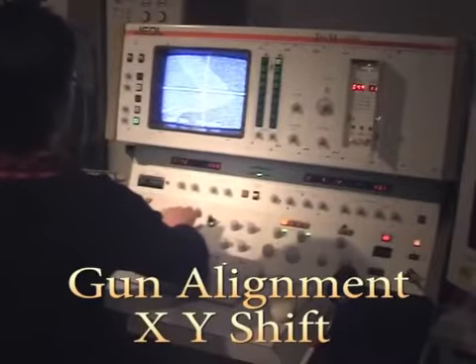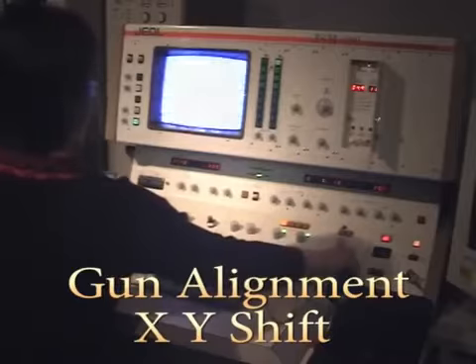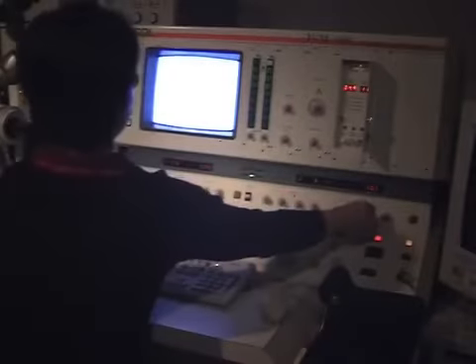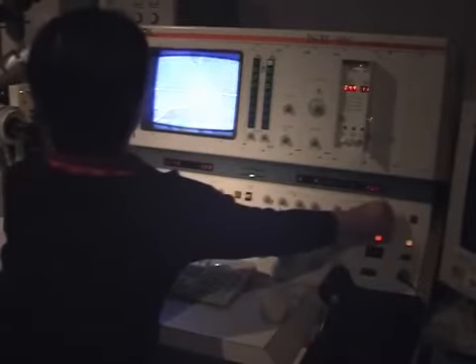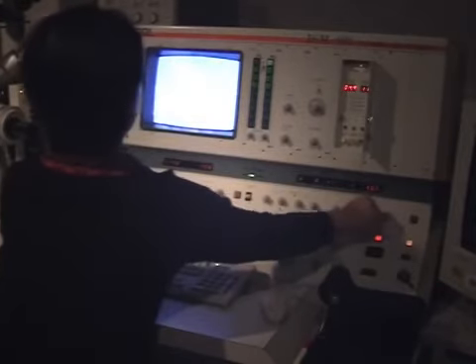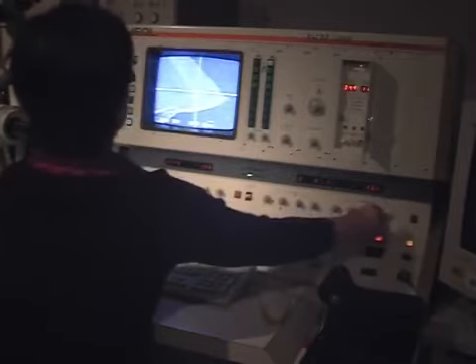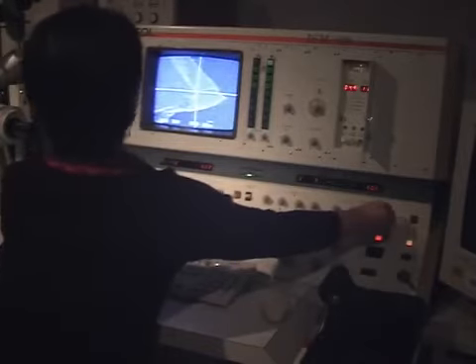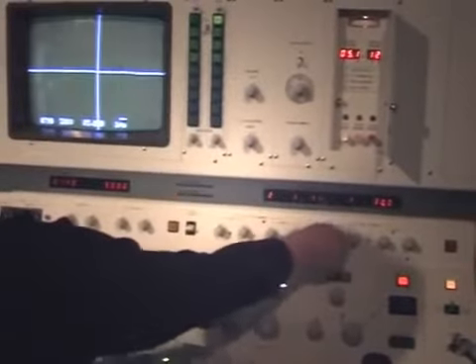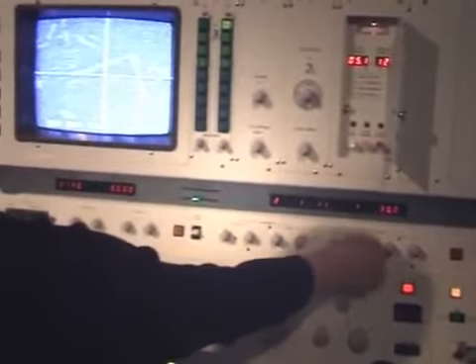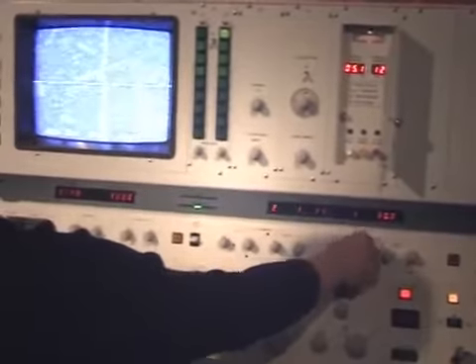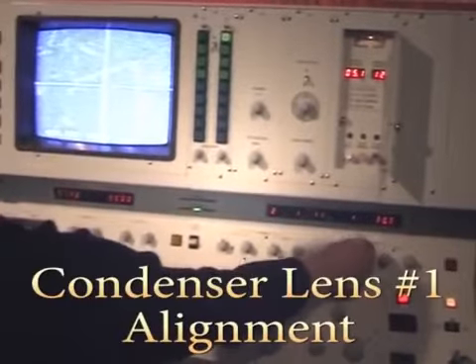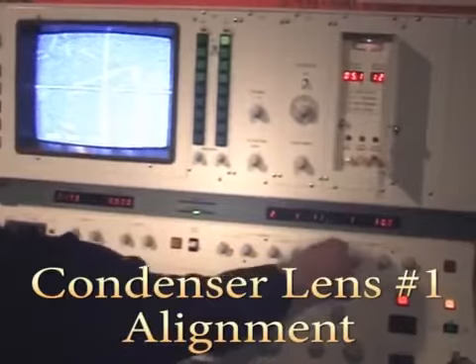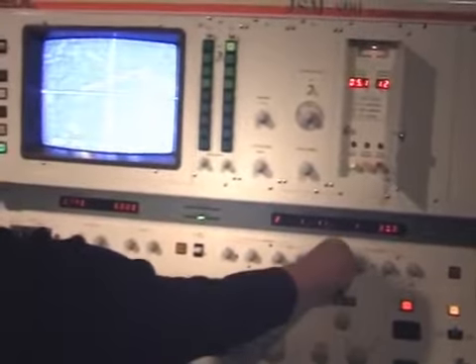Bring a noticeable feature of your specimen onto the crosshairs. Increase the probe current within the selected range. Bring the feature back onto the crosshairs by using the gun alignment XY shift knobs. Continue this until no image shift occurs. Adjust the gun alignment XY tilt knobs for the brightest image. Increase the magnification and continue to adjust the gun alignment XY tilt knobs.